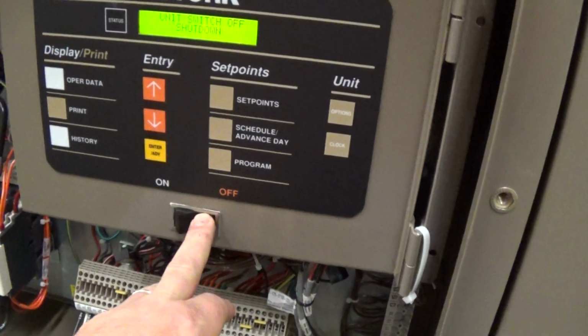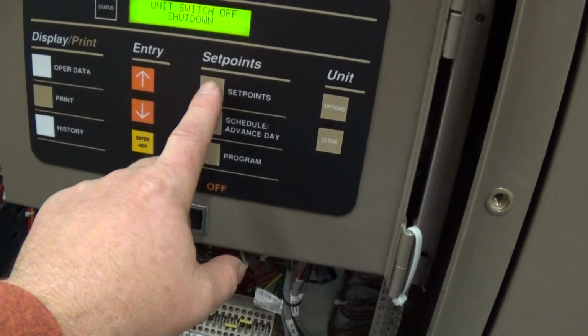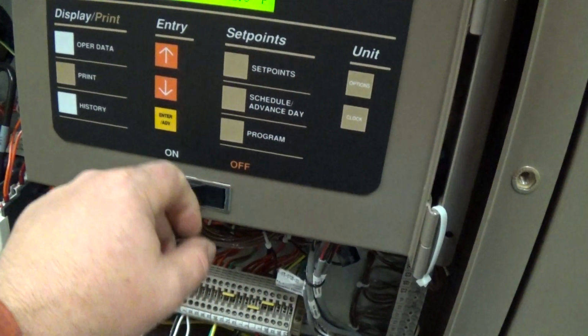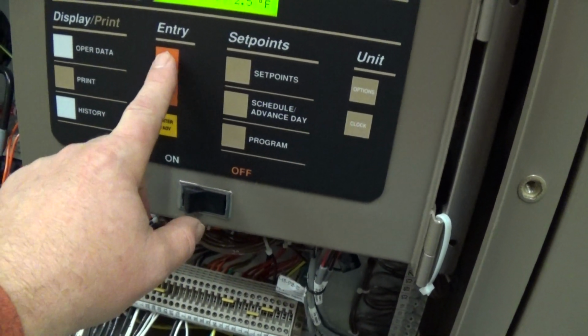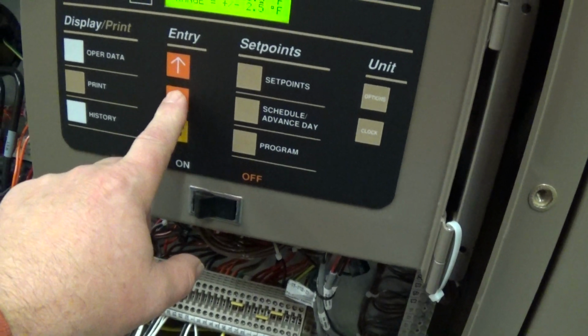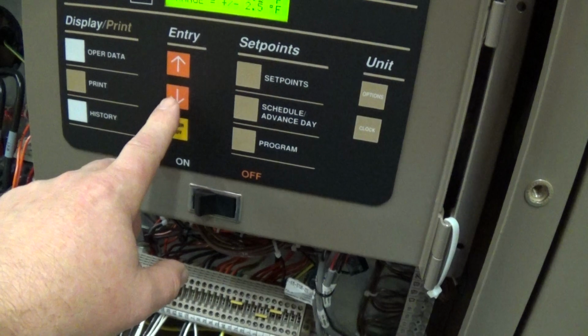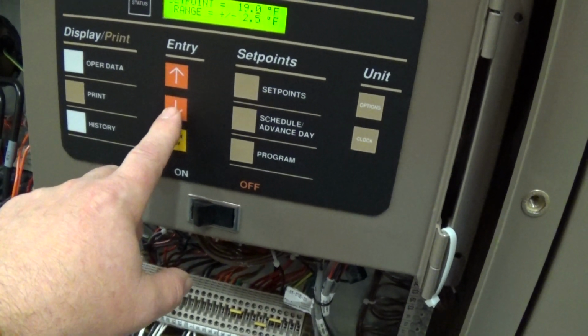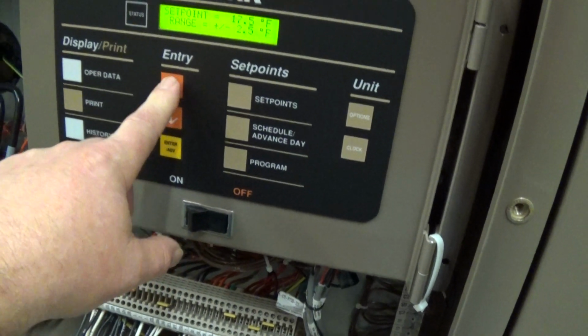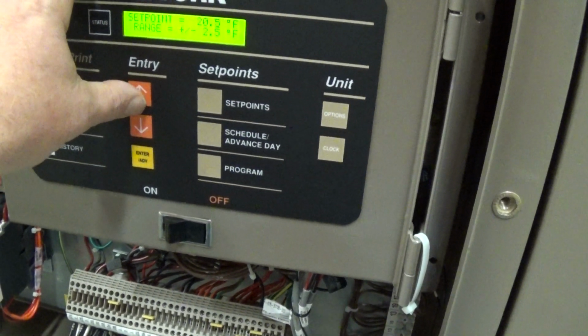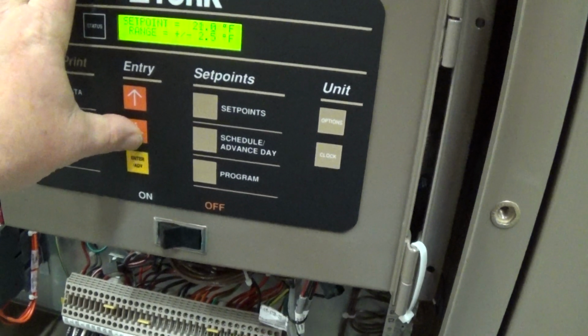Still with the rocker switch in the off position, we can go to set points, and you can see we have the set point right now at 20. This unit is actually okay to go down to 20. The lower you go, the less BTUs per hour you can do, of course. Even though the controller allows you to go down to 10, the refrigerant configuration in this style really isn't ideal for that. So this has a temperature range of 20 to 70.